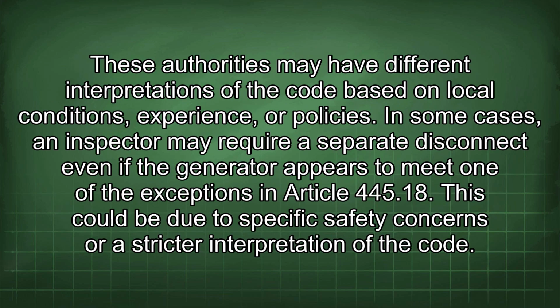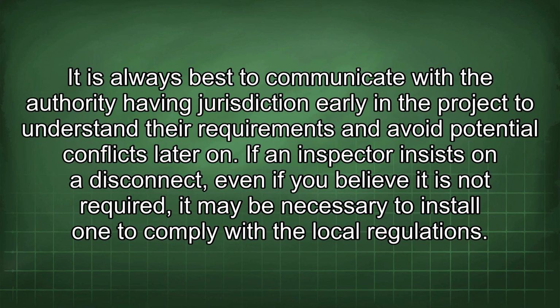These authorities may have different interpretations of the code based on local conditions, experience, or policies. In some cases, an inspector may require a separate disconnect even if the generator appears to meet one of the exceptions in Article 445.18. This could be due to specific safety concerns or a stricter interpretation of the code. It is always best to communicate with the authority having jurisdiction early in the project to understand their requirements and avoid potential conflicts later on.